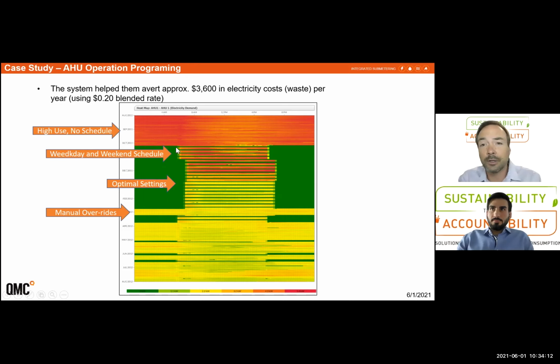They took action and quickly set the schedule to where it needed to be. So you can see the on-off times very clearly here, as well as the system turning off pretty much completely over the weekend. And then by this point in January, they'd actually optimized the settings of the air handling unit to be at the correct temperatures and settings, so it was using less energy during that time. So back to this kind of yellow or medium setting of energy consumption. And then a few months later, it was manually overridden, and you can see that happening here, going back to scheduled settings and then back to manual override. So it was neat to see how the design of this system was impacted by manual interference throughout the operation of the building over a 1-year period, and obviously impacted their ability to hit their energy targets.